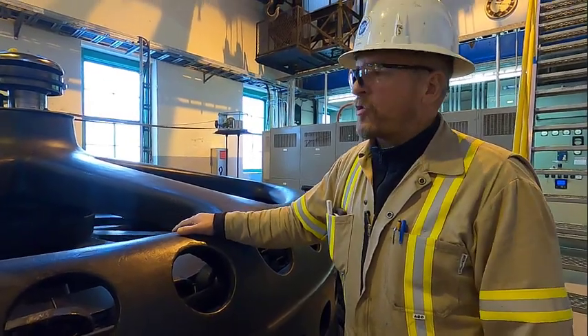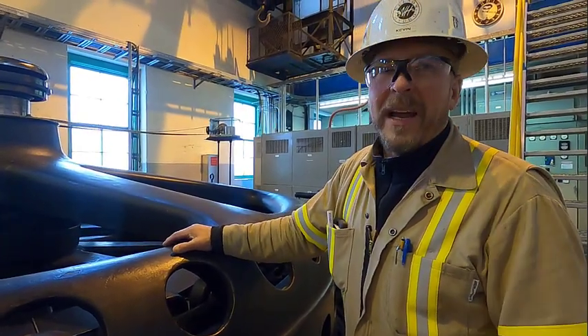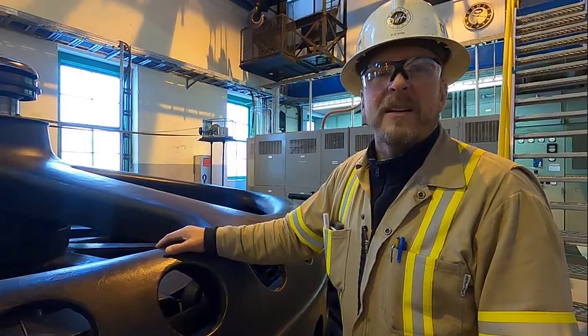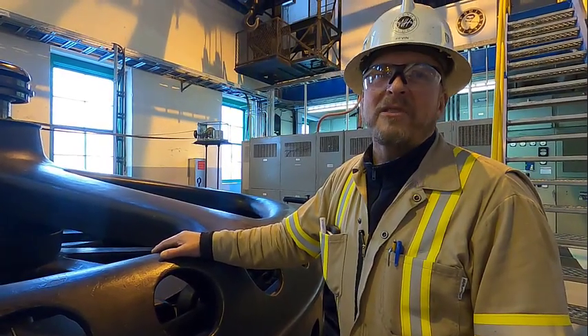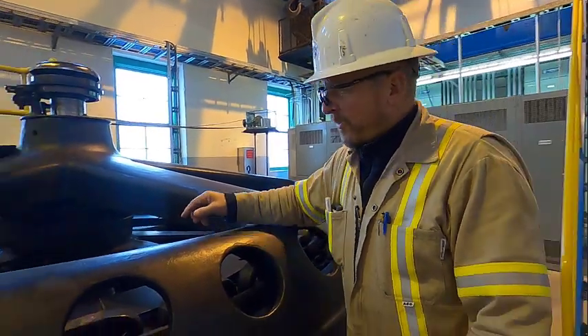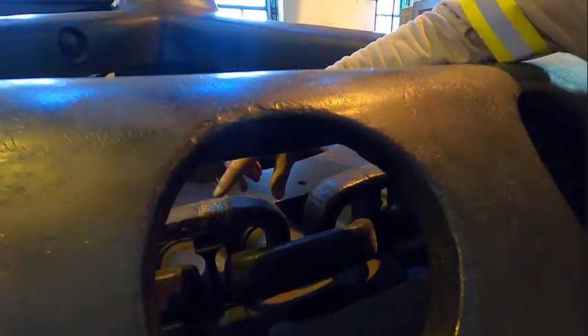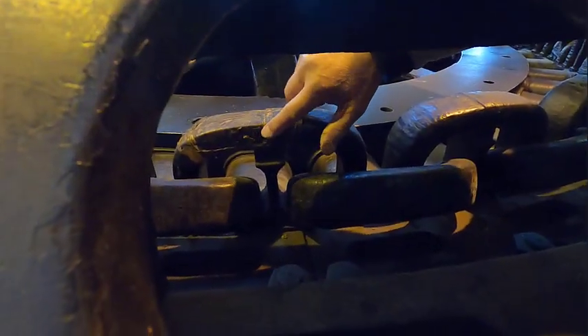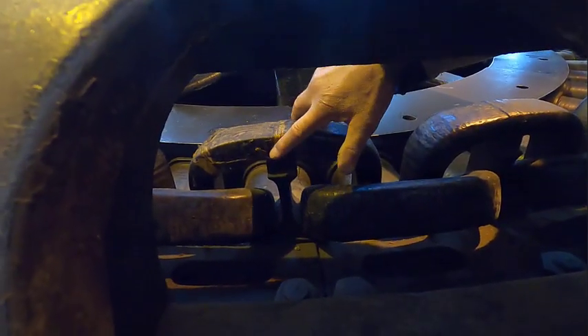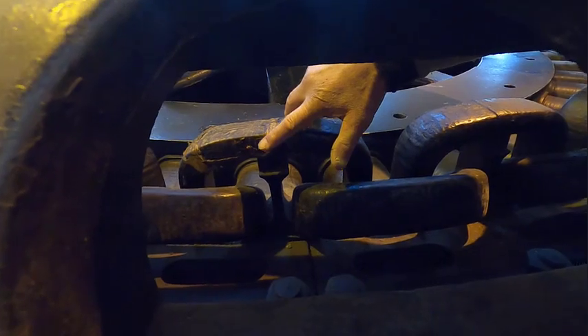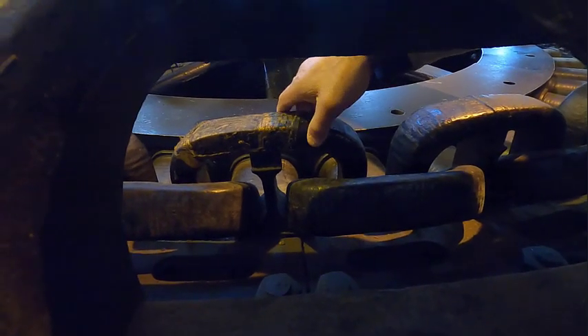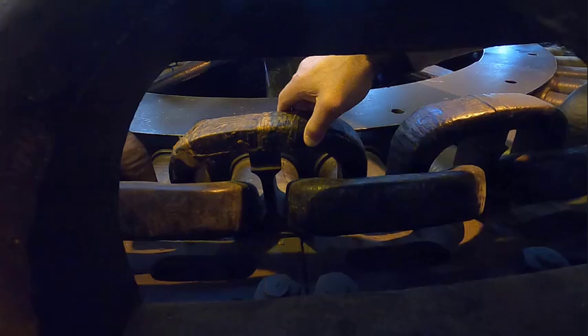Good unit to show people because we can safely go hands-on without being at risk of getting electrocuted or something. So right inside here are the actual coils. These are called the stator coils. That's what would generate the power when this unit was running. These coils would normally be at 12,000 volts if the unit was running.